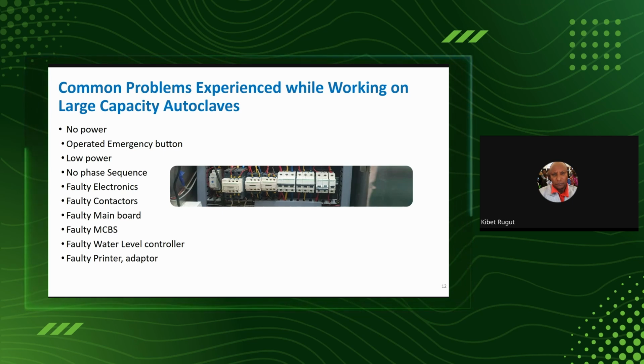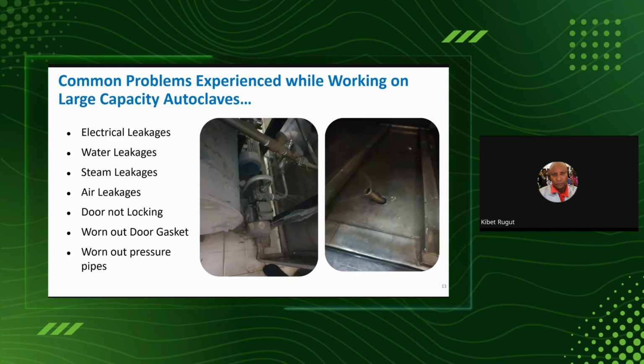So main circuit boards can also be faulty. MCCBs, the breakers, can also be faulty. If a water level controller sensor is not sensing well, or it is coated with rust, it can also misbehave. And if your printer for monitoring the temperature is also not working well, you will have a problem. So these are just the common things that you can come across when operating such a large-scale autoclave. Others can happen because of wear and tear.